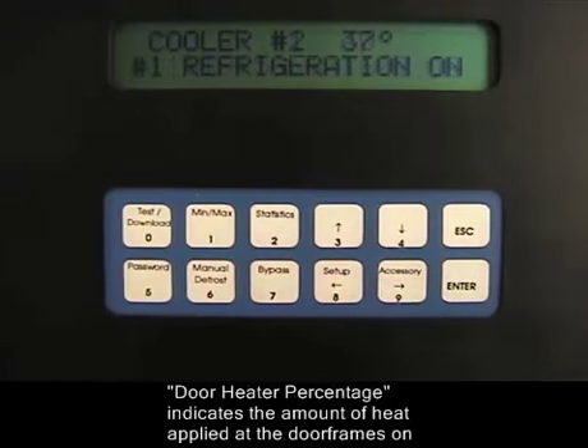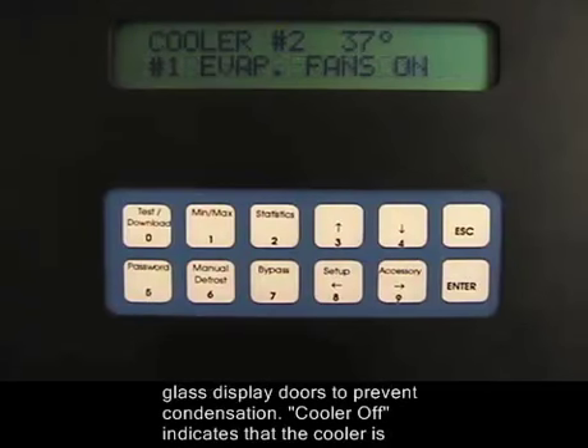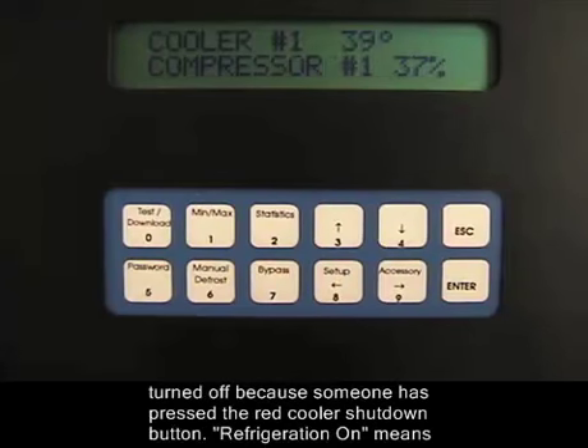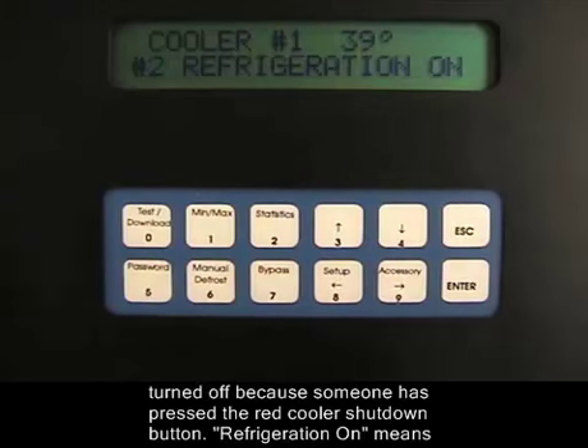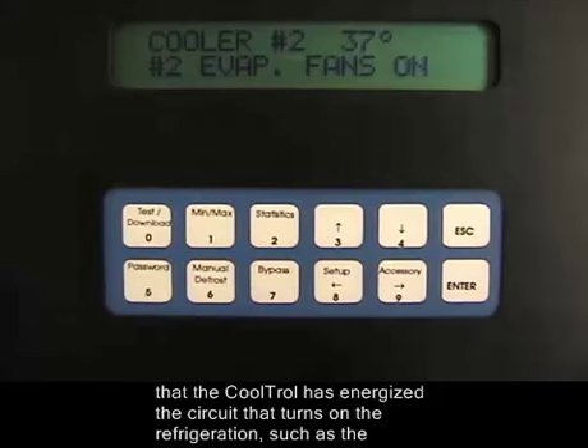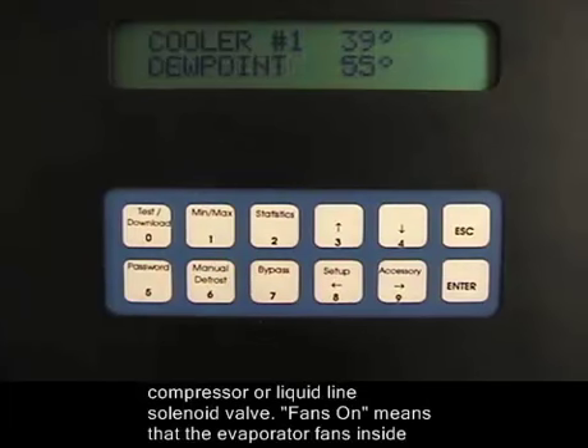Door heater percentage indicates the amount of heat applied at the door frames on glass display doors to prevent condensation. Cooler off indicates that the cooler is turned off because someone has pressed the red cooler shutdown button. Refrigeration on means that the CoolTrol has energized the circuit that turns on the refrigeration, such as the compressor or liquid line solenoid valve.